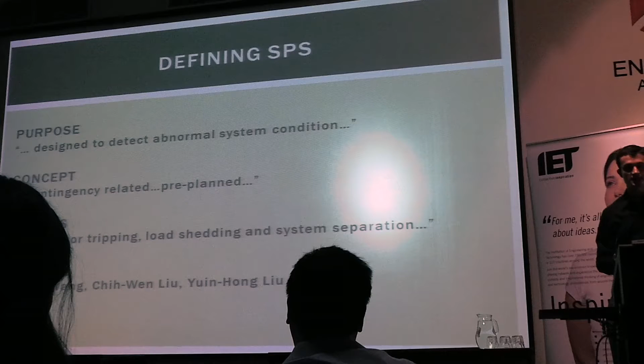An SPS, or any special protection scheme, is designed to detect abnormal system conditions, and thereafter implement pre-planned remedial actions in order to increase the stability of the power system. These remedial actions can take many forms, for example generator tripping, load shedding, or some other system separation.